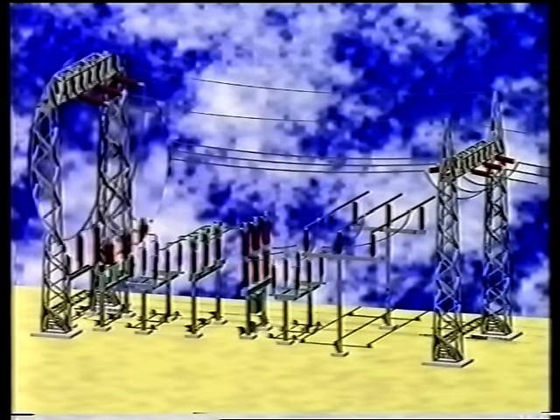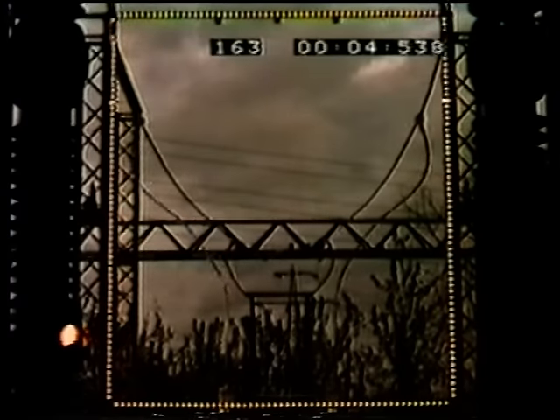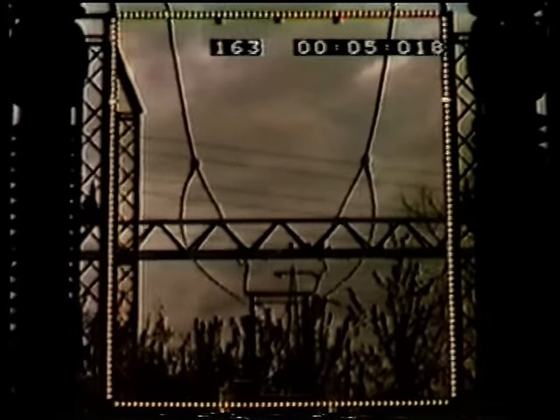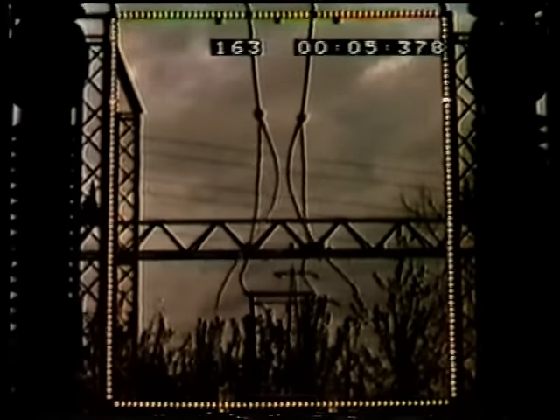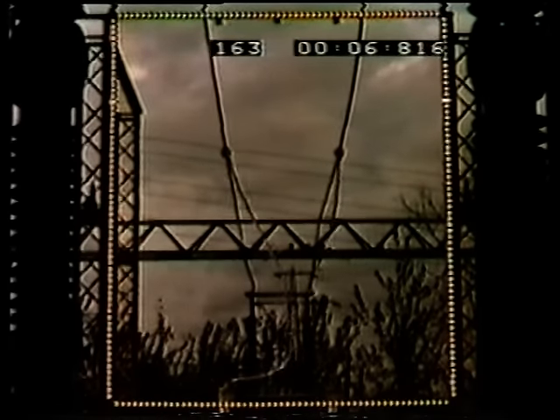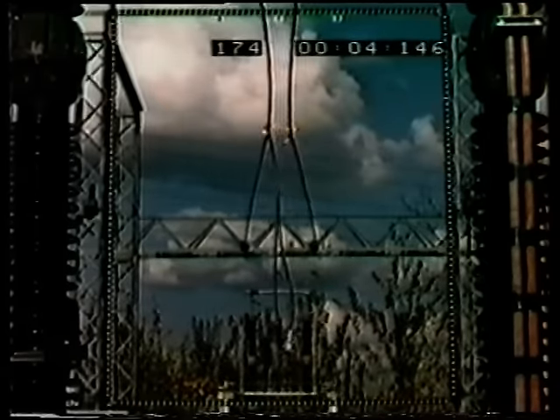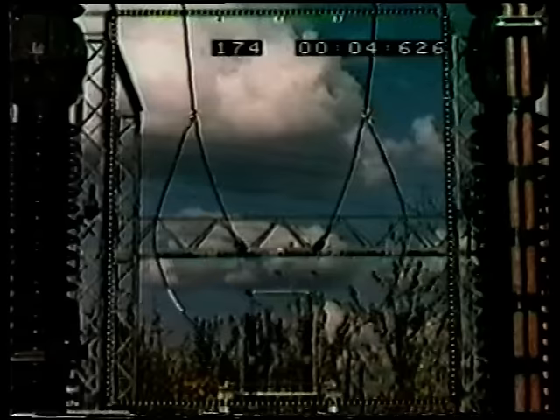While in the last test attention was paid to the span influenced by droppers, in the next two sequences the behaviour of the droppers themselves is looked at. The kind of movements depends on the short-circuit current path. First, only the span on which droppers are fixed is adapted with the short-circuit current. Nevertheless, the horizontal displacement due to the kinetic impulse of the fixing is impressive. The same dropper is then adapted with short-circuit current while the span carries the current to the connection point with the dropper only. The maximum displacement differs only little, but the kind of movement changes a lot.